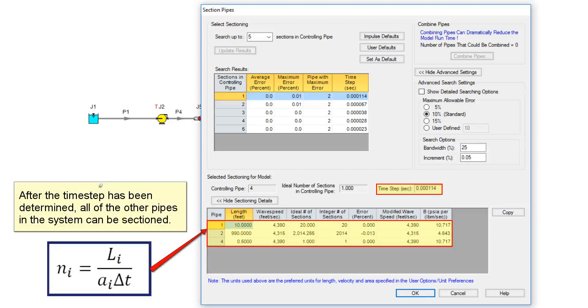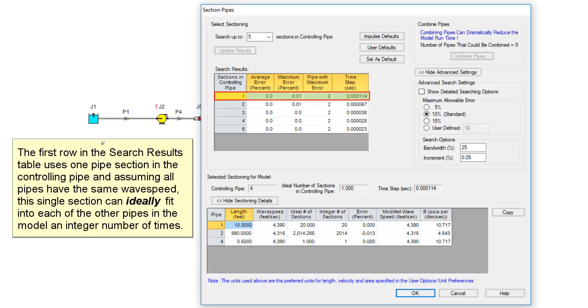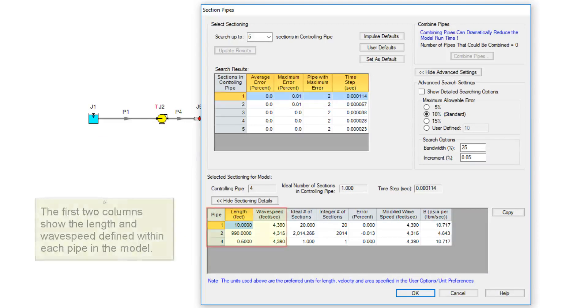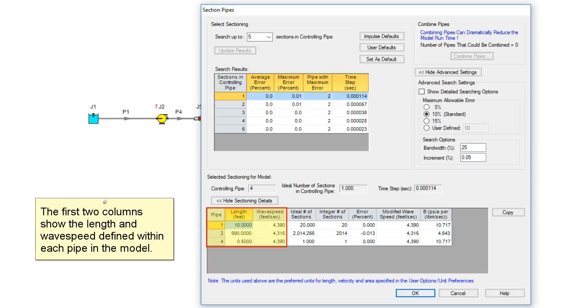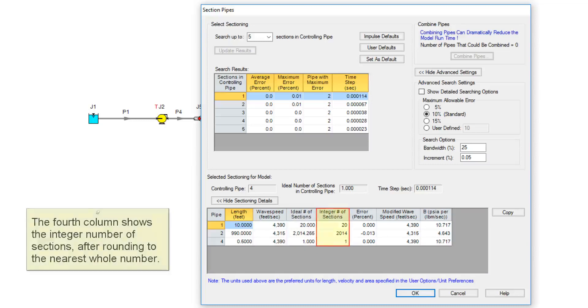After the time step has been determined, all of the other pipes in the system can be sectioned. The first row in the search results table uses one pipe section in the controlling pipe, assuming all pipes have the same wave speed. This single section can ideally fit into each of the other pipes in the model an integer number of times. The first two columns show the length and wave speed defined within each pipe in the model. The third column shows the ideal number of sections in each pipe allowing for fractional values. The fourth column shows the integer number of sections after rounding to the nearest whole number.